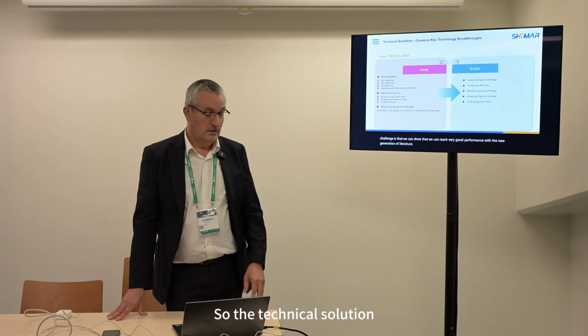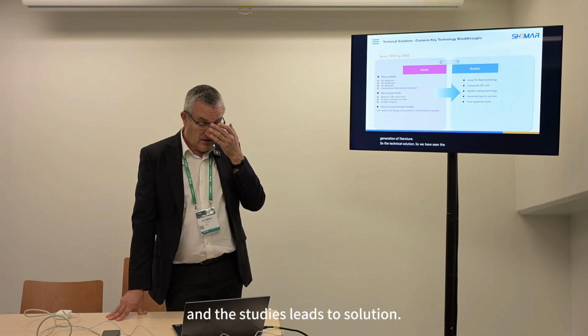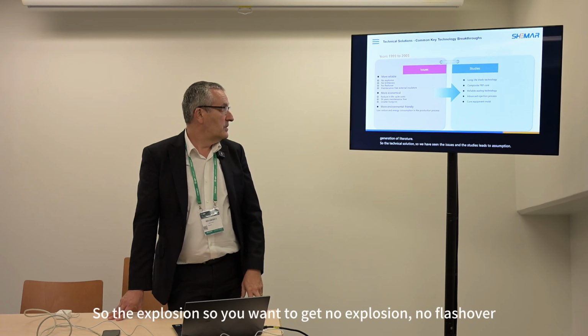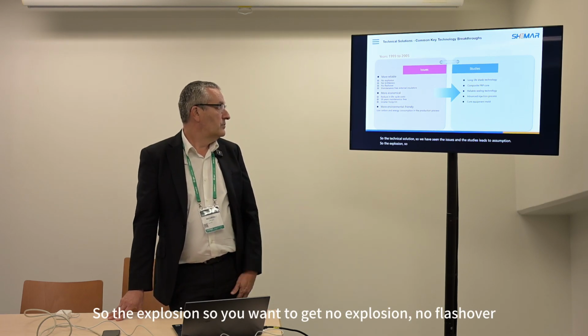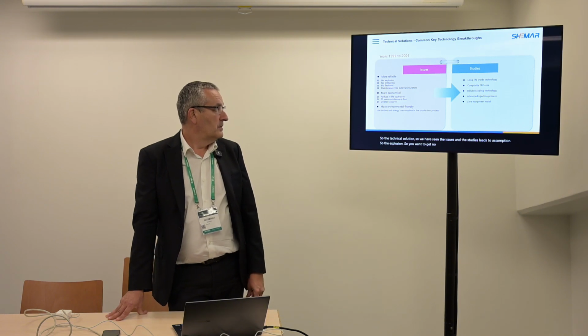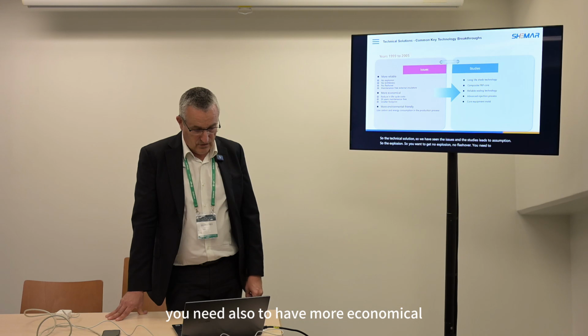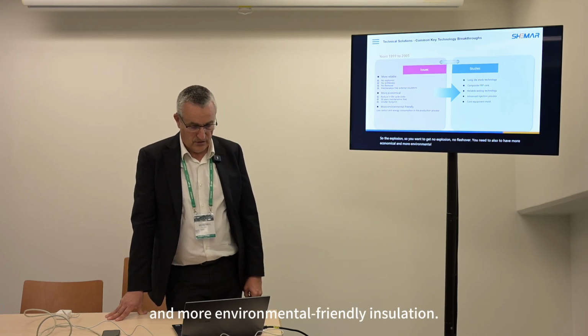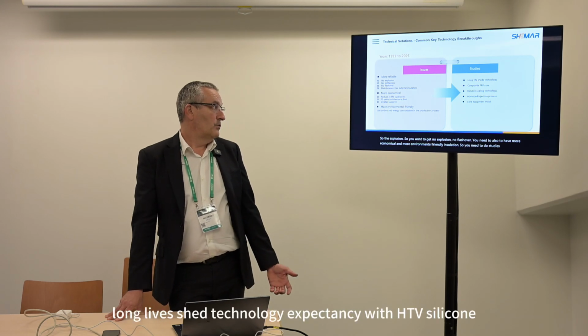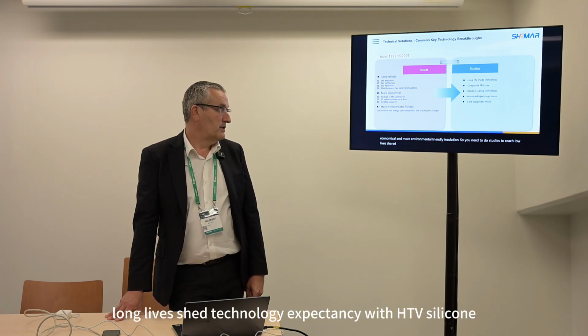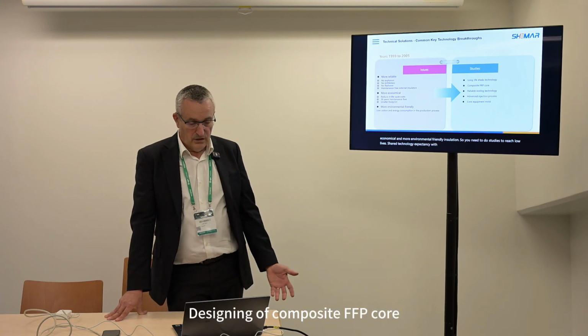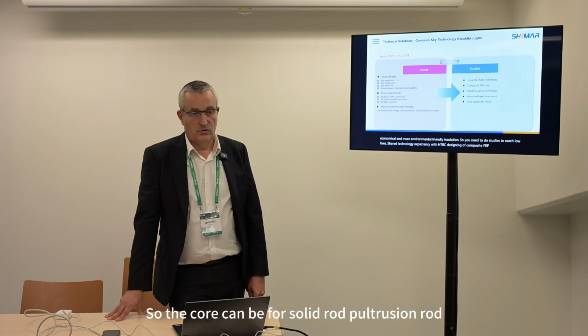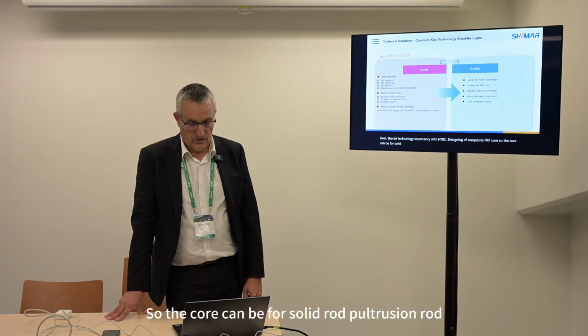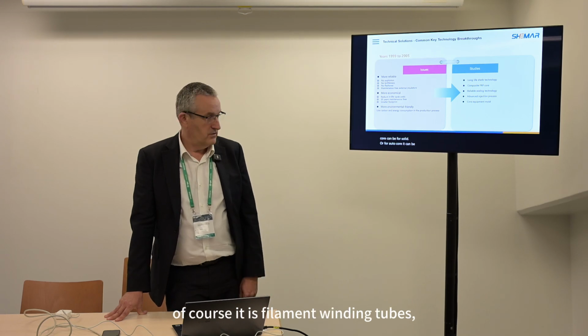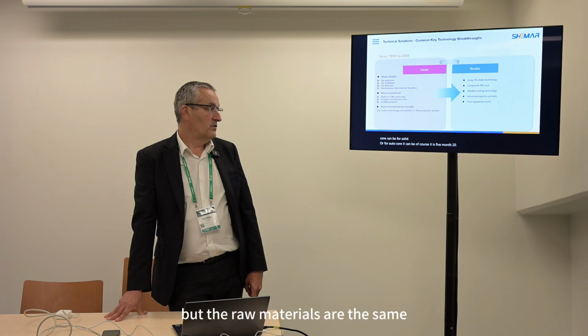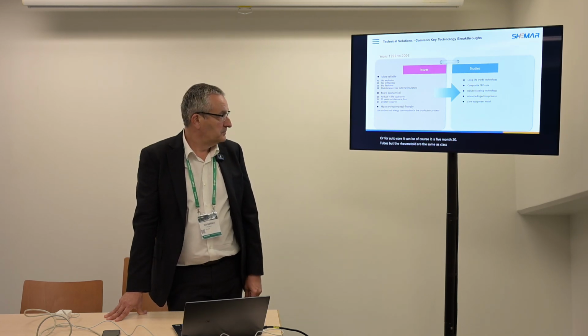So the technical solution: we have seen the issues, and the studies lead to the solution. You want no explosion, no flashover. You also need a more economical and more environmentally friendly insulation. So you need to do studies to reach a long-life shed technology expectancy with HTV silicone, designing of composite FRP core. The core can be a solid rod, a pultrusion rod, or a hollow core, which of course is filament winding tubes. But the raw materials are the same: glass fiber and epoxy resin.